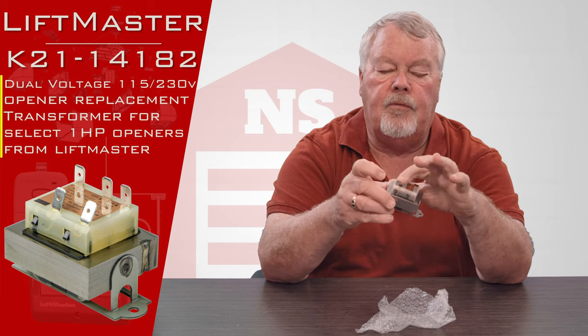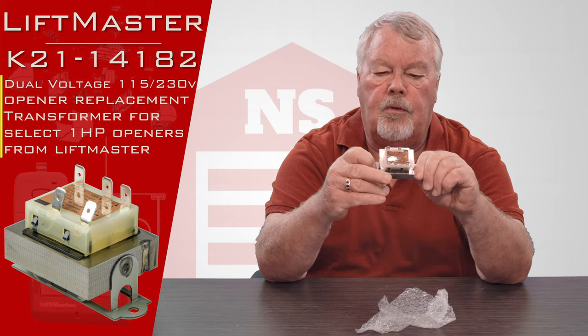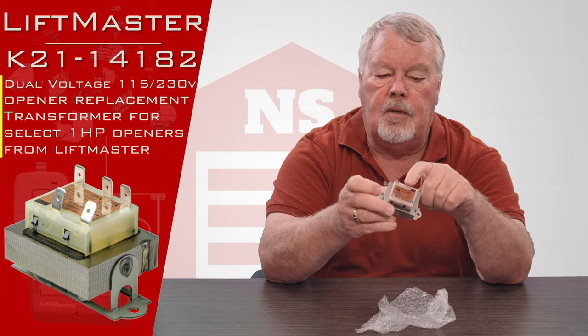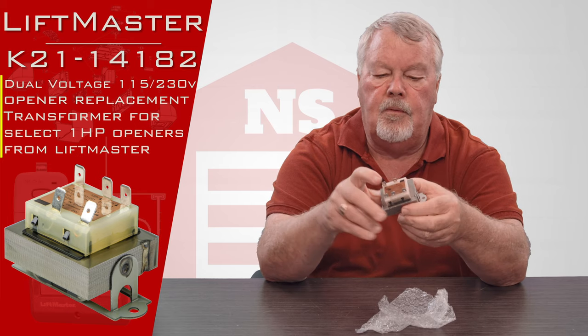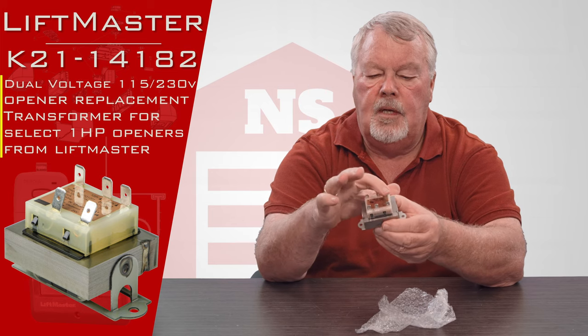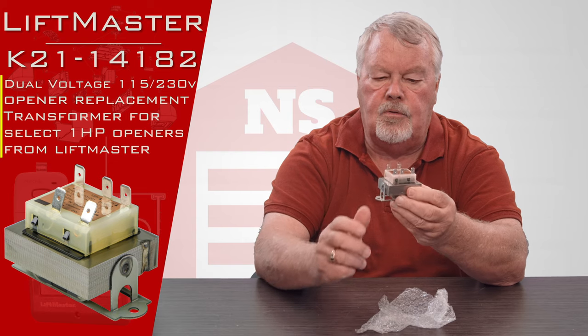There are wiring terminals on the front here. The terminals change depending on whether you're using 110 or 220. The two small ones here are going to be the output at 24 volts, and the others will be used based on whether you have 110 or 220.